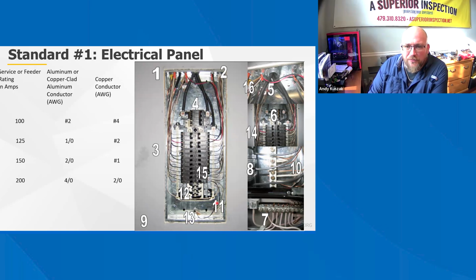And then over here on the bottom right of this middle picture, a grounding electrode conductor, which is commonly referred to as the GEC, is a conductor used to connect the grounding electrode to the equipment grounding conductor, the grounded conductor, or both at the service, at each building or structure that is supplied by a feeder or branch circuit, or at the source of a separately derived system. The GEC, grounding electrode conductor, is a conductor used for grounding at the service or separate building. The GEC is used to connect the grounding electrode system.